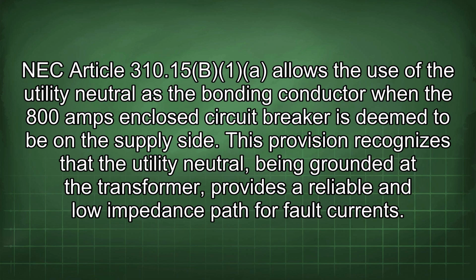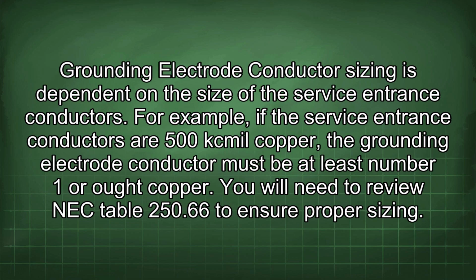NEC Article 310.15 allows the use of the utility neutral as the bonding conductor when the 800 amps enclosed circuit breaker is deemed to be on the supply side. This provision recognizes that the utility neutral, being grounded at the transformer, provides a reliable and low impedance path for fault currents. Grounding electrode conductor sizing is dependent on the size of the service entrance conductors. For example, if the service entrance conductors are 500 kcmil copper, the grounding electrode conductor must be at least number 1 or 1/0 copper. You will need to review NEC Table 250.66 to ensure proper sizing.